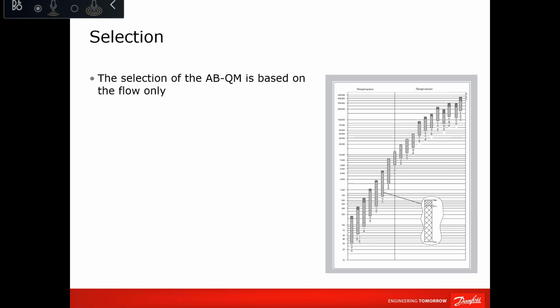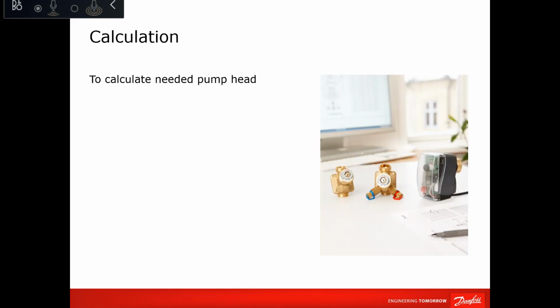Selection is done by Danfoss. This is something that we do, sizing, selection of the valve. And it's also easy. You can go and cross-check any selection. Just draw the line of your flow, and you will be crossing different sizes of the valve. Calculation: here, worth mentioning that we are doing this in Danfoss also. Calculation of the pump head, differential pressure transmitter location and set point. We are doing it to support our customer and to make sure that the system is hydronically sized and selected properly.